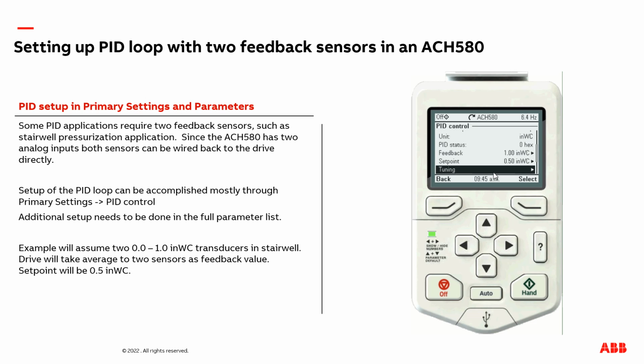Now, I'm not going to go into the tuning menu here, but this is where you'd make adjustments, for example, to your integral and gain to help speed up or slow down how fast the drive reacts to changes in the feedback source. This is something that would be adjusted after the basic PID control is set up and the drive is operating correctly based off of the two transducers.